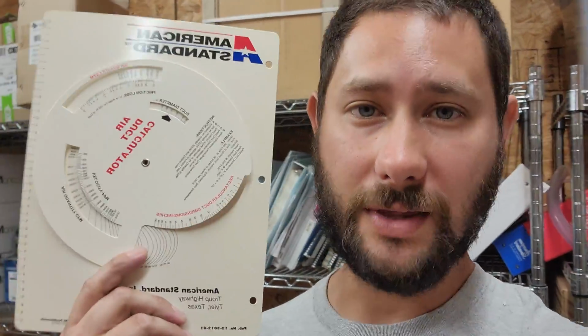So first, we have to know how to use a ductulator. If you know how to use a ductulator, then you know how to figure out if the ductwork that is attached to the system that you're troubleshooting is the right size. Because if it's not the right size, that's going to cause some issues with your pressures, especially if the duct size is too small for the unit. Airflow is one of the biggest problems in the field. If you know how to size ductwork, you know how to use a ductulator, then you're going to be able to rule that out as, hey, the duct size is great. We shouldn't have any problems there.